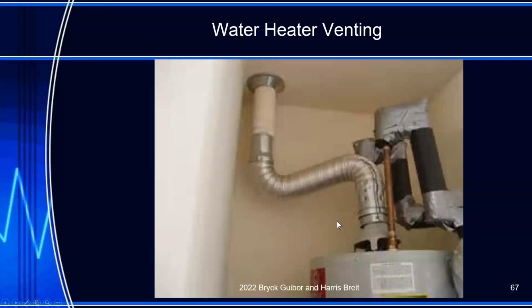Okay, there we go. If you take a look here, the draft hood is loose. See the big gap here? It's laying outside. Here's copper hooked directly to the top of the nipple on the water heater. There's no dielectric there. Now, some areas require a flex line here.